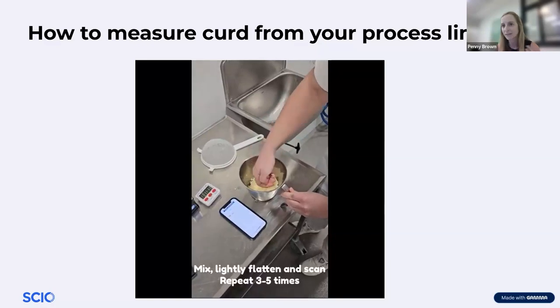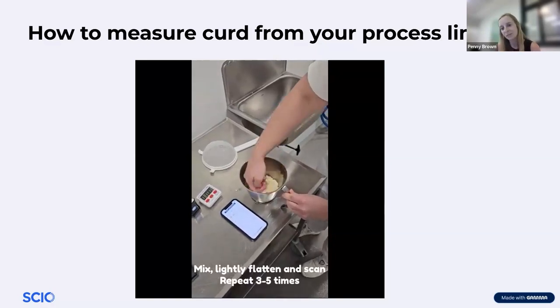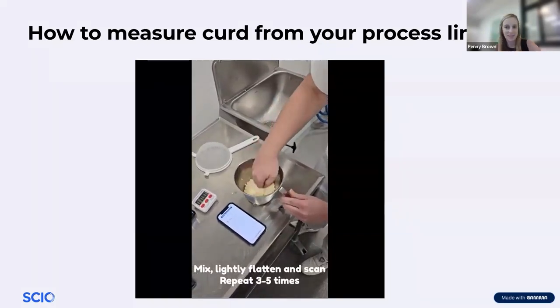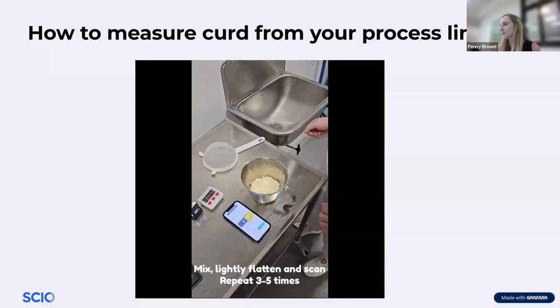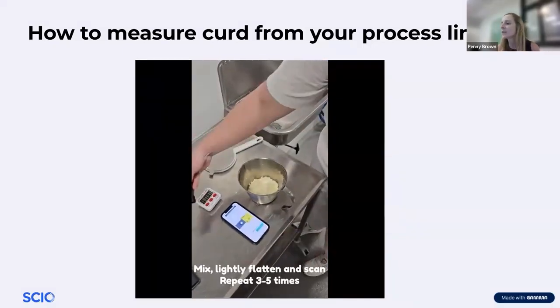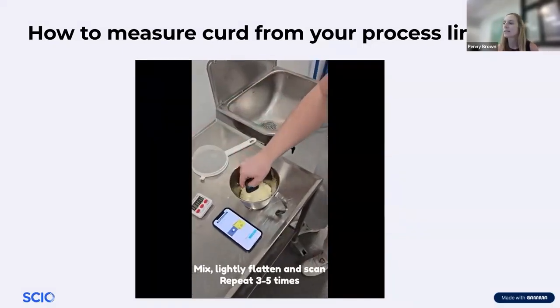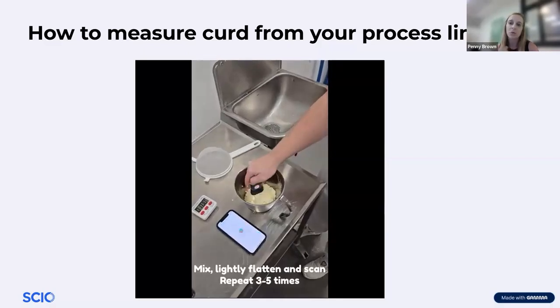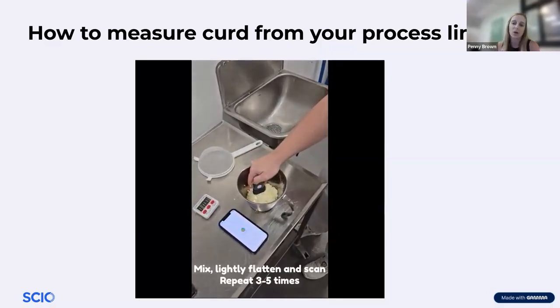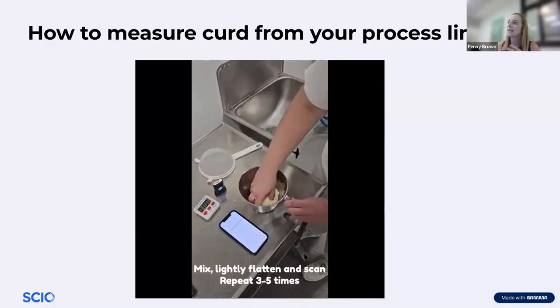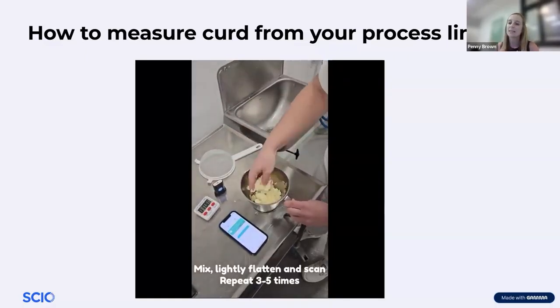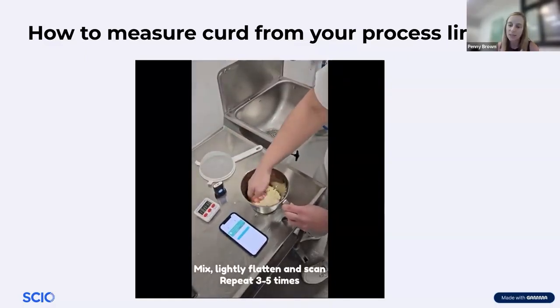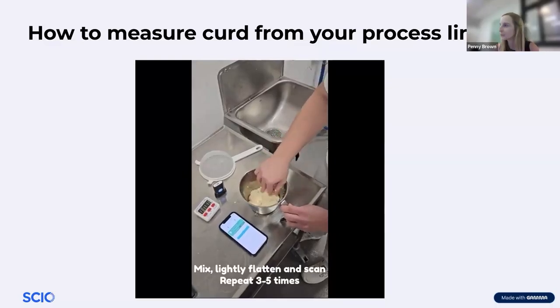What you're really looking for is differences. So you want to make sure that the result you're getting today is the same as the result you were getting yesterday. The other thing that you'll notice he's doing is mixing the sample, and this is just to make it more representative. You don't want a non-homogeneous sample to be scanned. So he's scanning, and then between each scan, he's mixing it up again. That just gives you the best, most representative result possible.